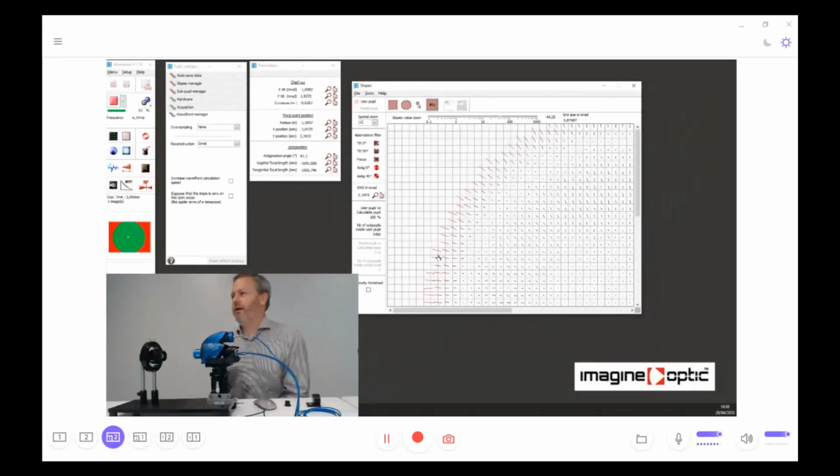Okay, this is again a very interesting question. Of course, as I said, all this stuff here has some aberration. The modules especially are optimized in order not to have a lot of aberration, and all this has been specified quite tightly. I think, depending on the F number of these modules, the aberration at the output of this is between 30 nanometers to 100 nanometers root mean square.